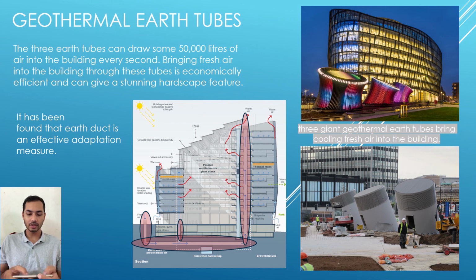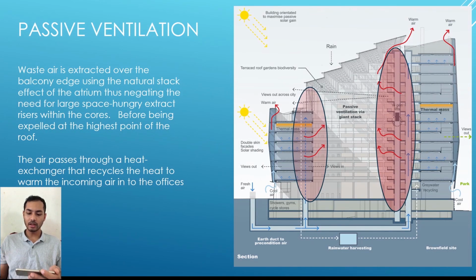Next is passive ventilation. As you can see in the diagram, I highlighted the passive ventilation in the building. Waste air is extracted over the balcony edge using the natural stack effect of the atrium, negating the need for large, space-hungry extract risers within the cores, before being expelled at the highest point of the roof. The air passes through a heat exchanger that recycles the heat to warm the incoming air into the offices below.